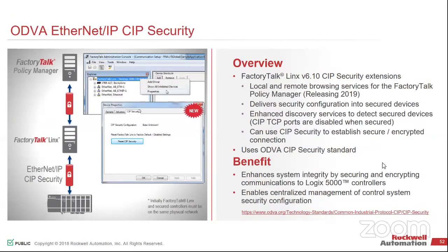So pulling that leftmost piece off, from the controller through Linx to essentially the server system, this is going to be CIP security. CIP security is on the protocol layer. So we have the ODVA CIP protocol that everybody knows and loves. CIP security essentially will be a security layer appended to the back of that CIP protocol, which will allow for encrypted secure communication.